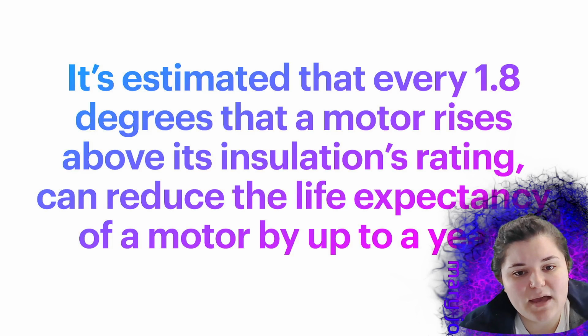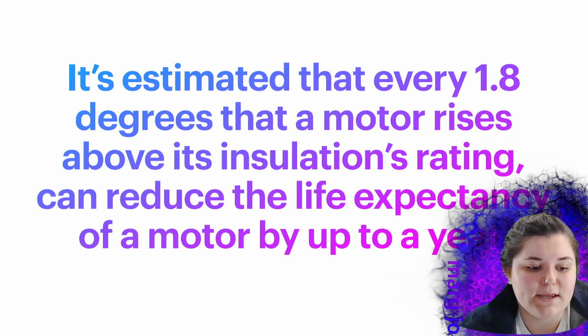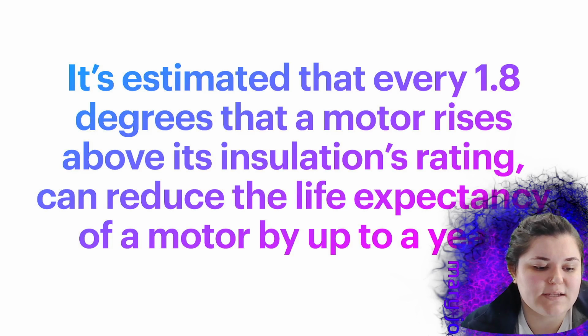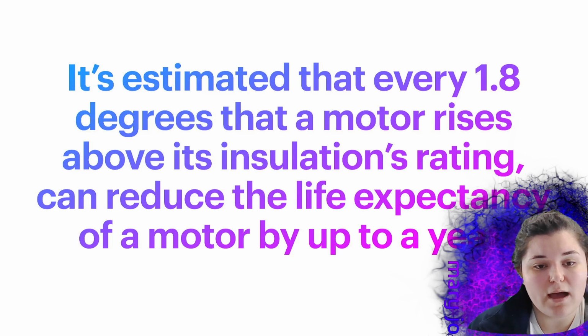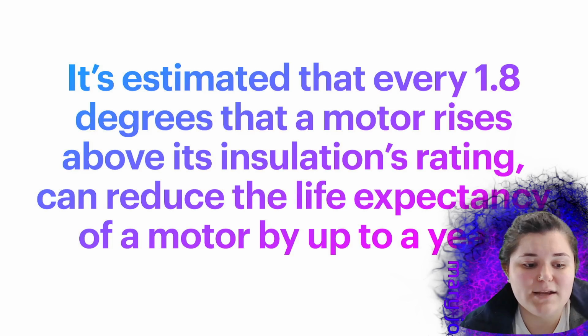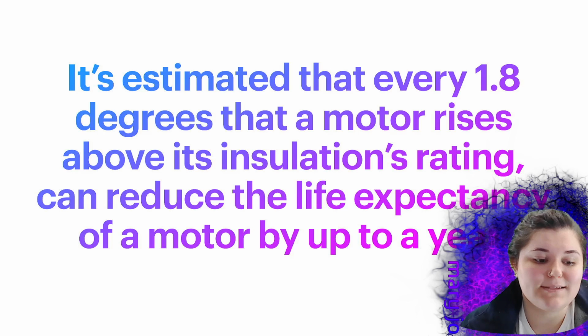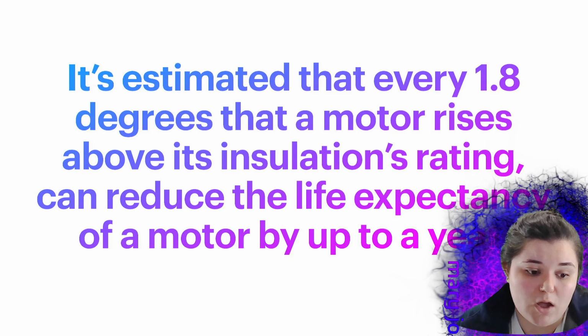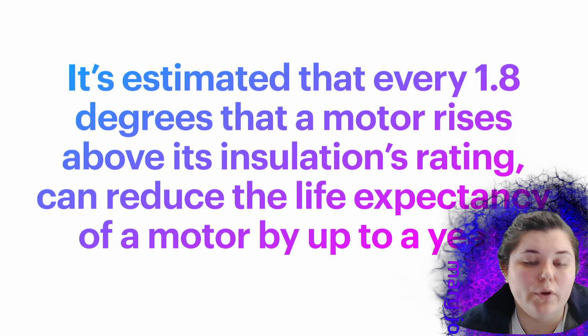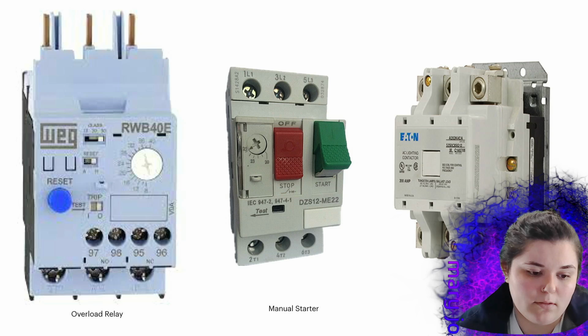So it's estimated that every 1.8 degrees Fahrenheit that a motor rises above its insulation's rating can reduce the life expectancy of a motor by up to a year. So that is why it's really important to have overload protection, because if a motor overheats, it's going to destroy its insulation, and that's going to decrease the motor life by up to a year, even if it just raises 1 degree above that rating.